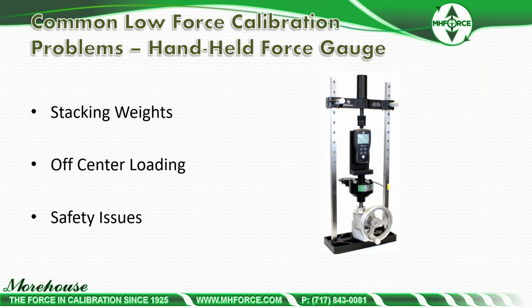But now I wanted to talk about low force calibration problems. And here's a handheld force gauge calibration. Some of the problems we have, typically if you're using weights, are stacking weights, off-center loading, and safety issues. If anybody saw a post I made, it's about these back plates. We were making them in our facility last week.